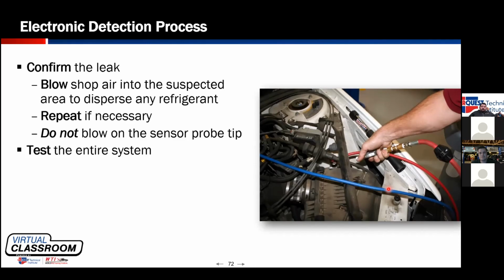One other thing I hear a lot that I'll talk about now as far as safety is I hear a lot of guys saying, I pressurized the system with shop air to leak detect it. Never, ever put shop air into an air conditioning system. Couple of reasons. One, shop air tends to be pretty nasty. I'm sure being in Florida, Bryn, you probably have some moisture issues in your compressed air. I know as humid as it's been here in Pennsylvania, I can drain my compressor every day and my shop air is wet. We don't want to put that moisture in. We don't want to put that junk in the system. Coupled with the fact that when 134A mixes with compressed air in a pressurized environment, 134A can become explosive. So definitely have some safety issues there.